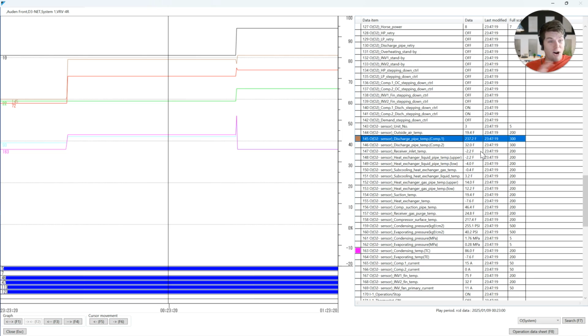This oil is awful. It's carbonized. It's trash. This compressor needs to be replaced. And I wouldn't just say this compressor because they're all the same. I'd say all the compressors in the system. And you're saying, well, Roman, that is a very big, drastic leap. And here's the thing about compressor oil. Once you let the cat out of the bag, you can't put it back in.